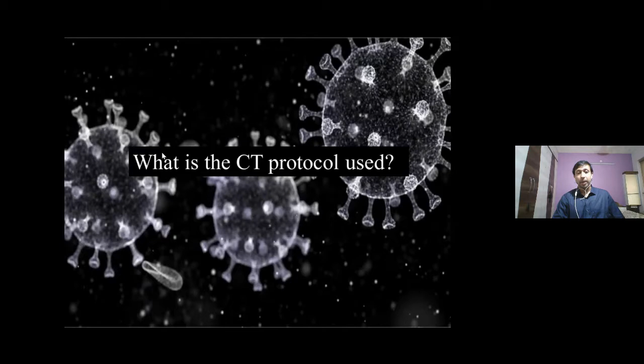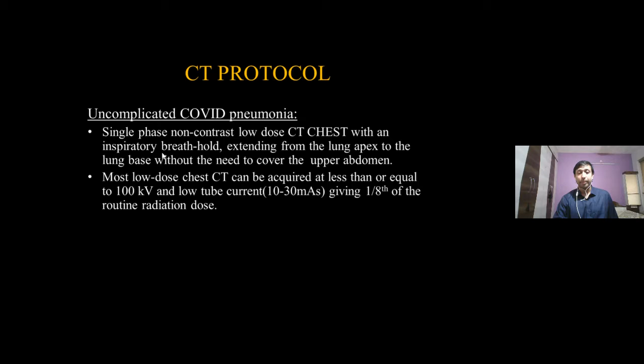For radiation protection purposes, as these patients may need follow-up CTs, a low-dose chest CT is acquired at less than or equal to 100 kV and low tube current, that is 10 to 30 mAs, giving nearly 1/8 of the routine radiation dose.